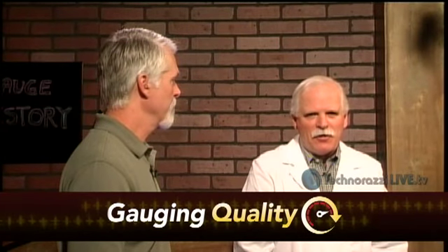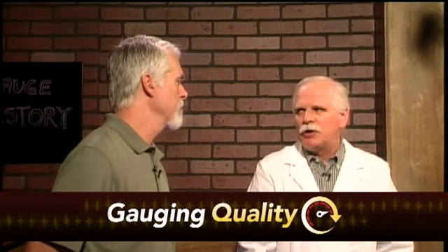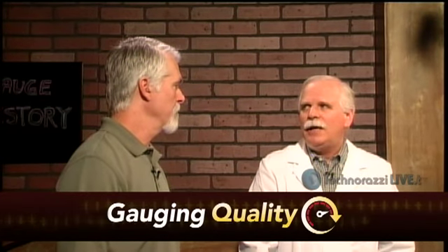What I was faced with then was the choice of, well, what do you do now? It looks like it's good, but I know from the history, which is very valuable, that it can blank out. What we did is gave it a full-up accept because it was acceptable at that point in time, and that's all you really have. But with the history, I was able to put a note on there that says, historically, this has shown that the gauge can blank out at the higher ranges. If that happens, further investigation is needed.